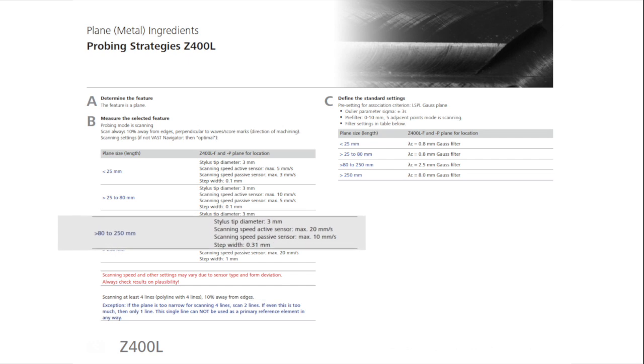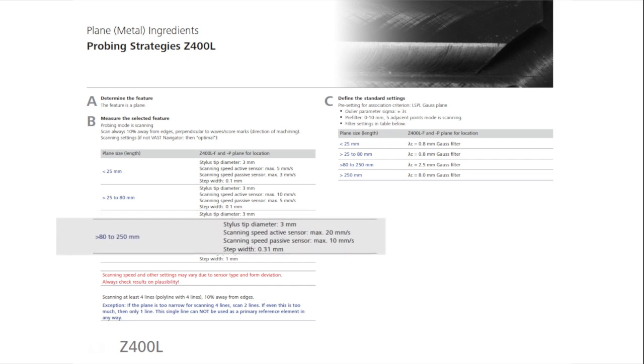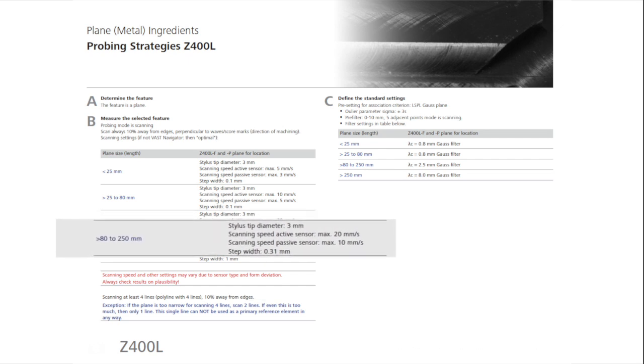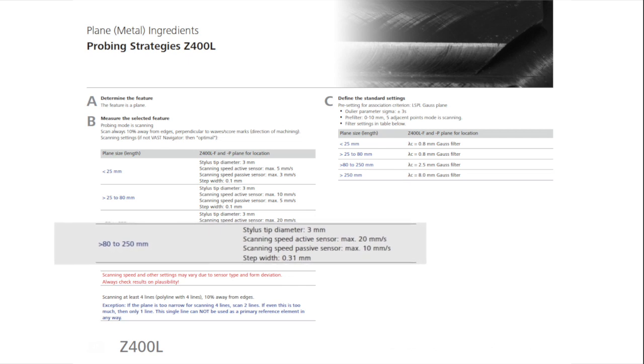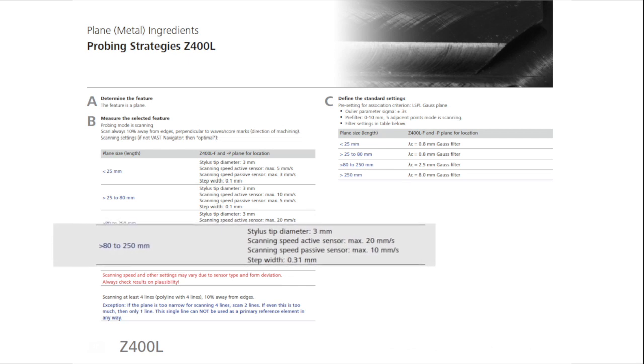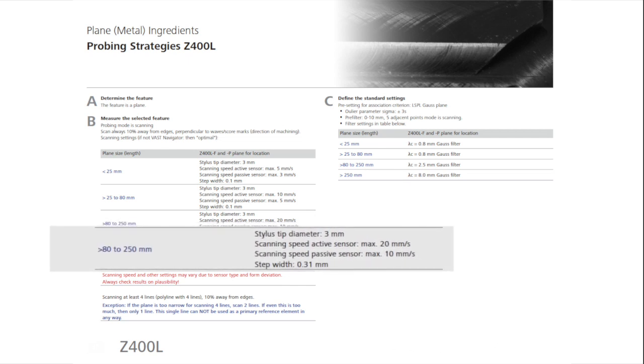For a surface area of 80 to 250 mm, it suggests, when measuring with an active sensor, a stylus of 3 mm, a maximum scanning speed of 20 mm per second, and a step width of 0.31 mm.